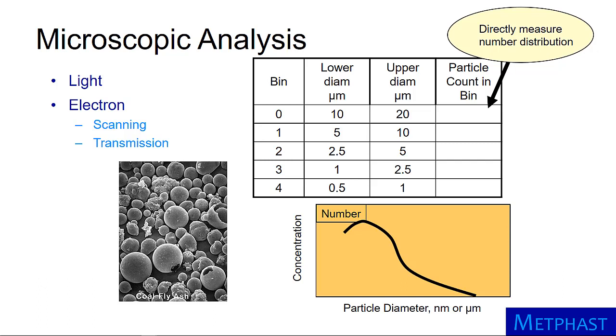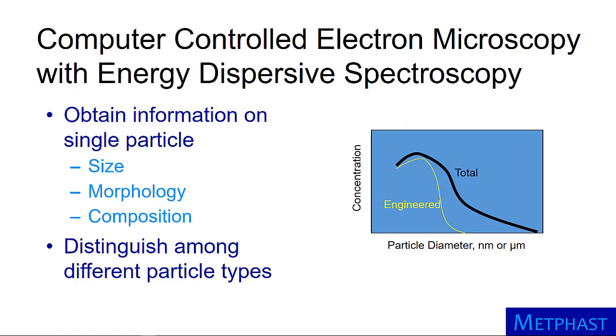From analysis of pictures, the number concentration of particles can be binned by particle size. The state-of-the-art in microscopy is computer control of the microscope with energy dispersive spectroscopy. The computer drives the microscope until a particle is found, then the particle size and morphology are assessed by image analysis. Finally, the composition of the particle is determined from emitted x-rays by energy dispersive spectroscopy. Such technology is exciting because we can figure out what portion of the size distribution is due to certain types of particles, such as engineered particles.